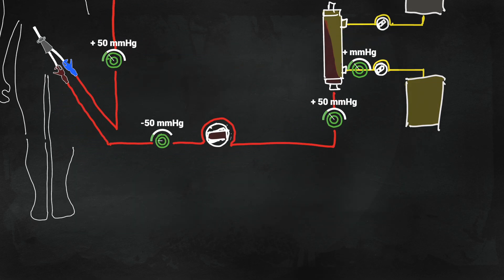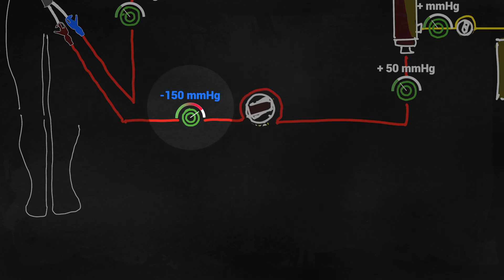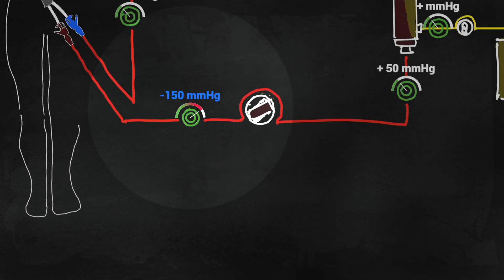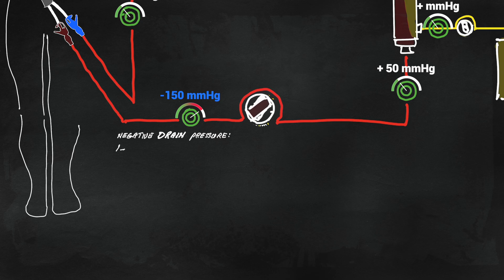When access pressure gets increasingly negative, the reason is due to the pump pulling harder to maintain a constant flow, which could be due to catheter clotting or kink in the line.